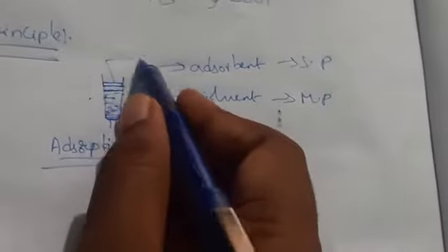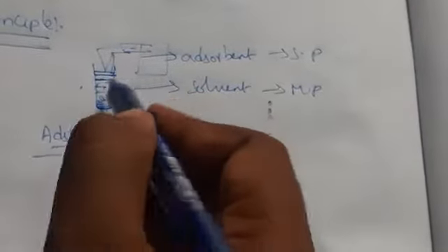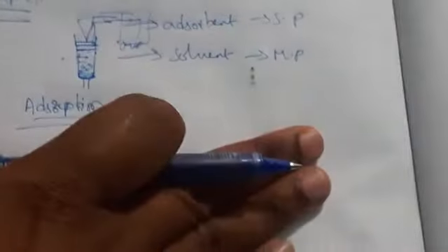In this method the separation takes place in which the stationary phase is contained in a column. This is the column we are using. For this we use a high pressure pump for the solvent, that is the mobile phase. The mobile phase travels through this pressure to the sample. This is the basic principle we use here.